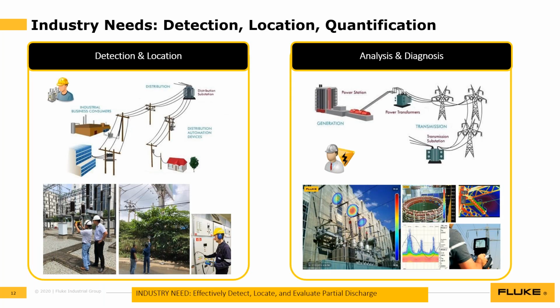And we identified two clear segments of needs. So the industry knows that there's partial discharge and it's causing these issues. Well, what do they need? They need to detect and locate. So this is a basic need specifically demanded by distribution utilities and by industrial high voltage users. And so it's what's the best way to easily detect that there is partial discharge there, but then also locate exactly where it's coming from so that something can be done about it.